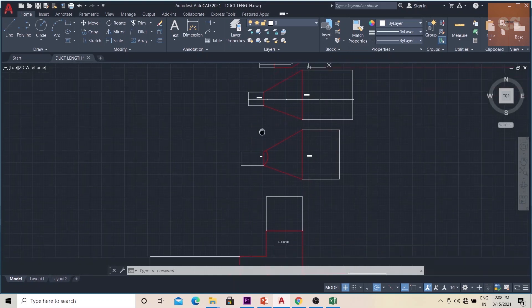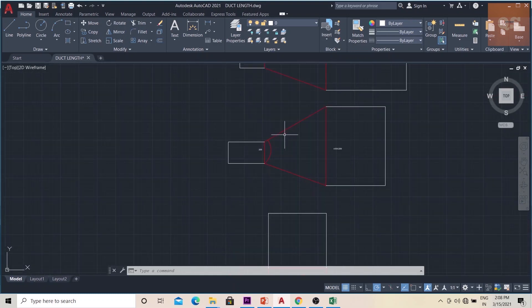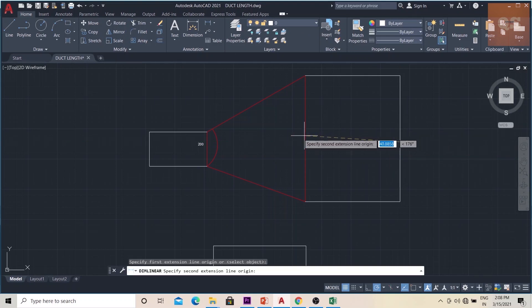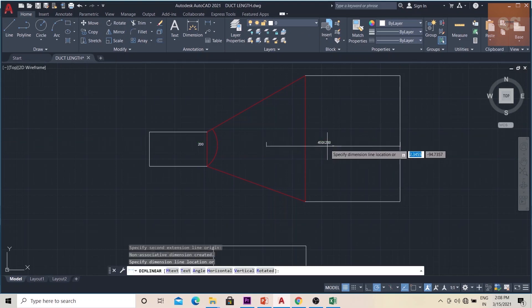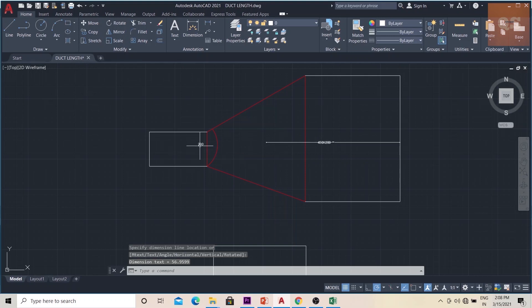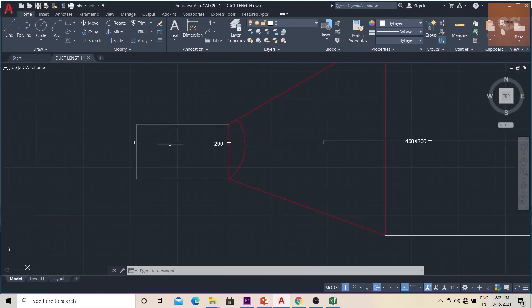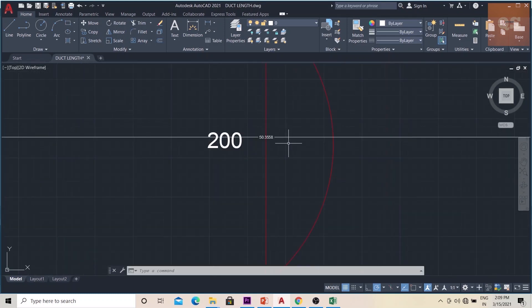Now imagine this piece — one duct is 450x200 and this is a transition, connected to a circular or oval duct. Again, the length till the center part of this piece will be 450x200, and then this is a 200mm diameter circular part. That part will be from the center till the remaining, so that part will be the 200mm duct piece length.